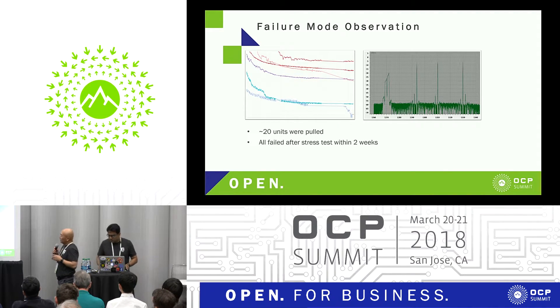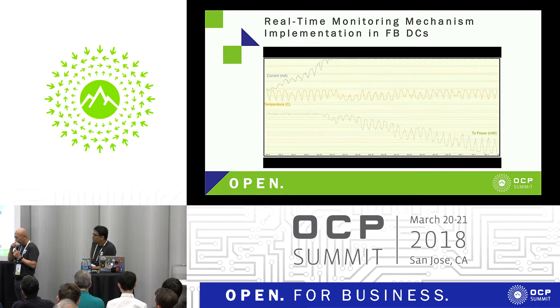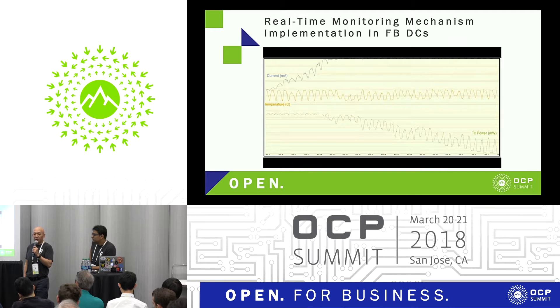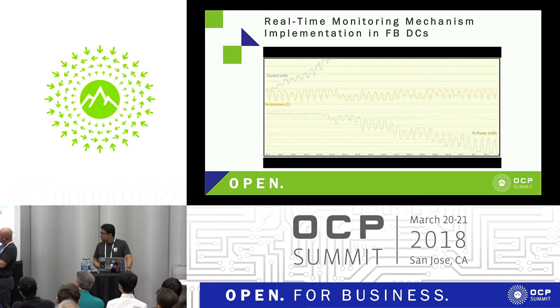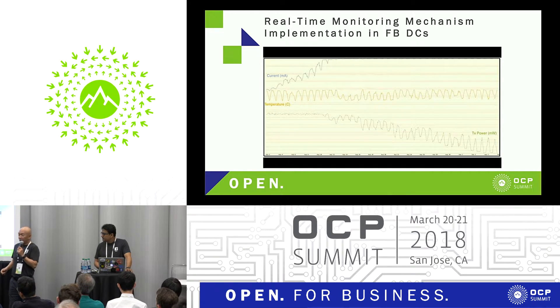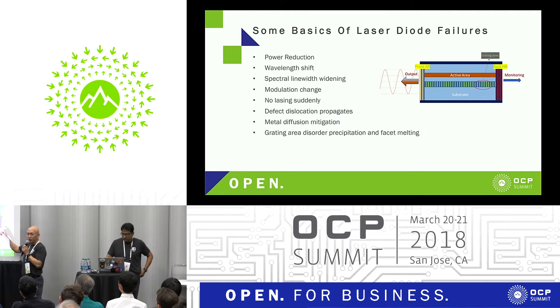This is very interesting, especially this first correlation, which got our attention. The biggest problem for us is that lost traffic in a real data center is really challenging — much higher cost than any switch or hardware equipment — and we want to predict it. This curve shows that when your temperature changes, you get power variation. The bias current goes up because of a loop-back system inside that increases current to maintain power. If you take a very stable structure, you can understand the mechanism behind the failures.